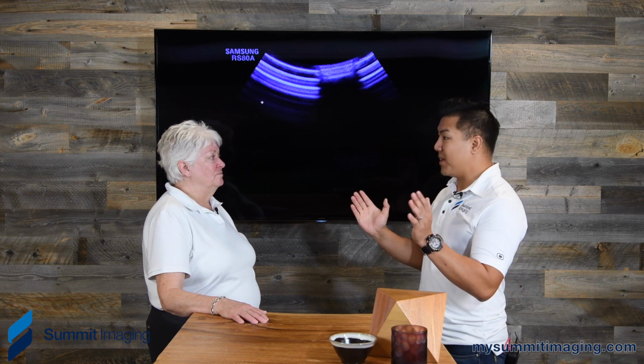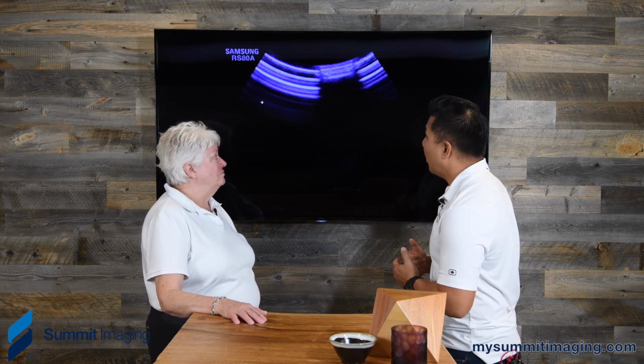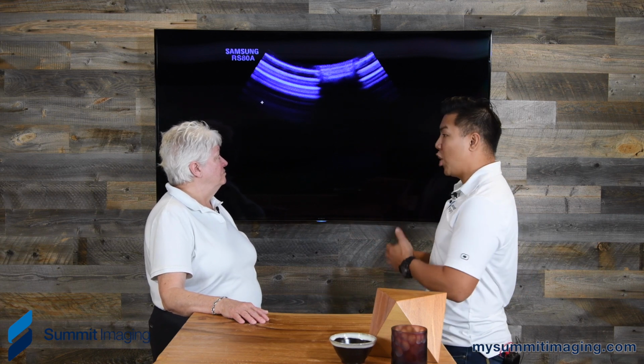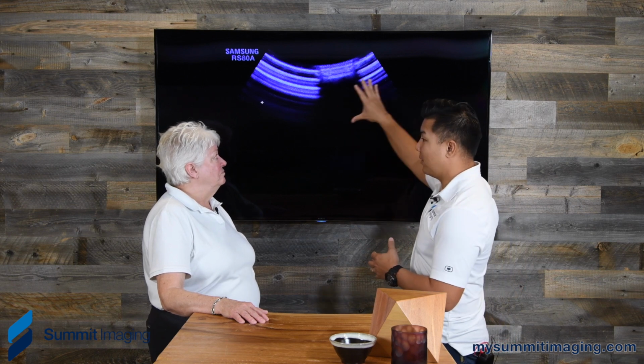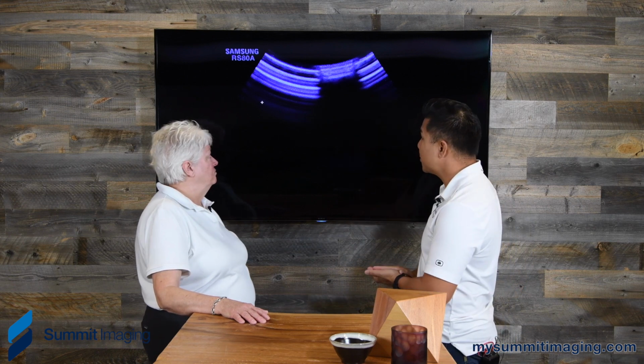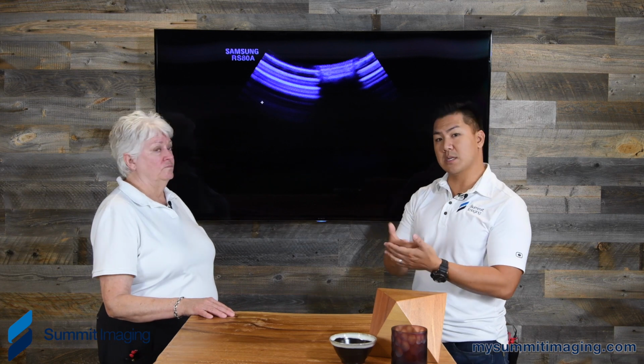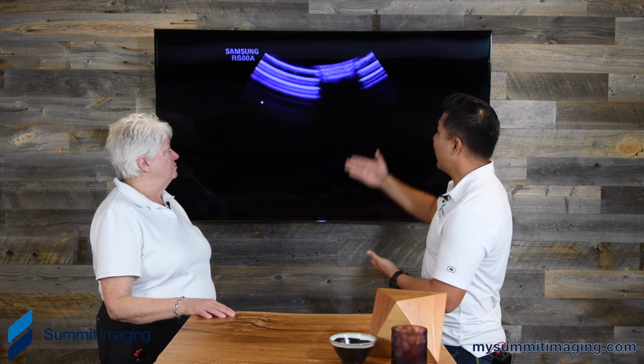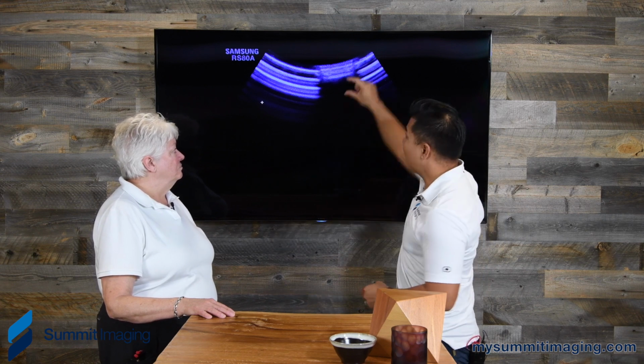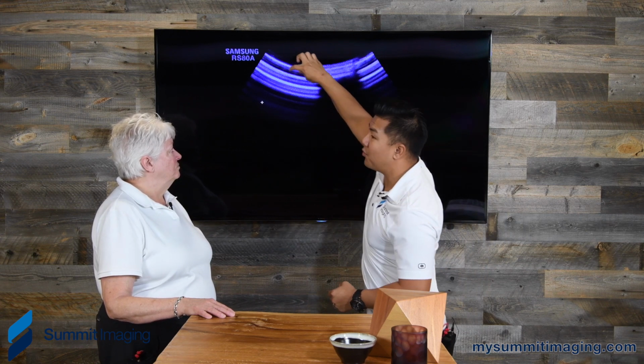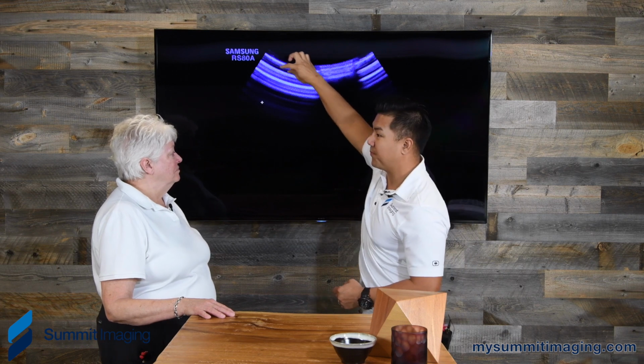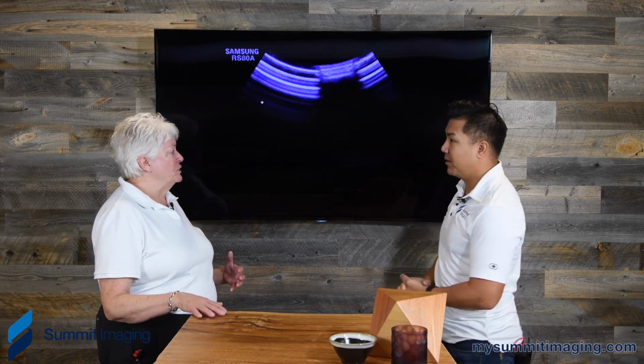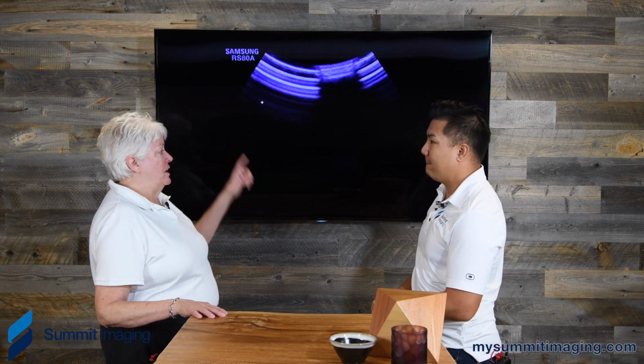There's a million ways that you can damage a probe, but what we're seeing is the result of some sort of impact that has compromised the seal of oil inside what we call the top dome of the lens of the transducer, and it is now being displaced with air. And that air is what you're seeing here. When you rock a probe back and forth, you'll see this air bubble move across the crystal. So there's some troubleshooting a sonographer could do if they knew to give that a try.